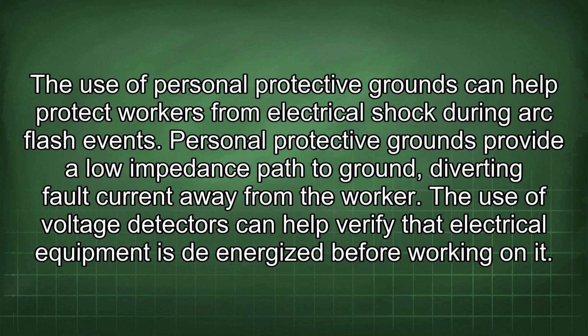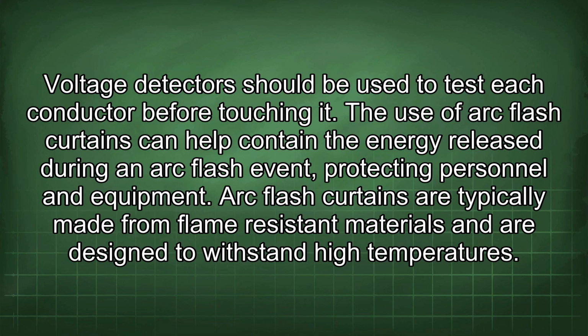The use of personal protective grounds can help protect workers from electrical shock during arc flash events. Personal protective grounds provide a low-impedance path to ground, diverting fault current away from the worker. The use of voltage detectors can help verify that electrical equipment is de-energized before working on it. Voltage detectors should be used to test each conductor before touching it.